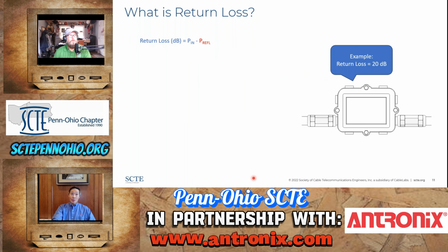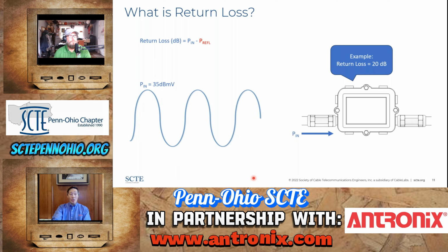We could also show this visually a little bit. So you have a device here that has 20 dB return loss of signal going in. If I have an input power going into the device of plus 35 dBmV, for a 20 dB device, the actual reflected power is the difference between the two. And the power reflected is actually 15 dBmV.